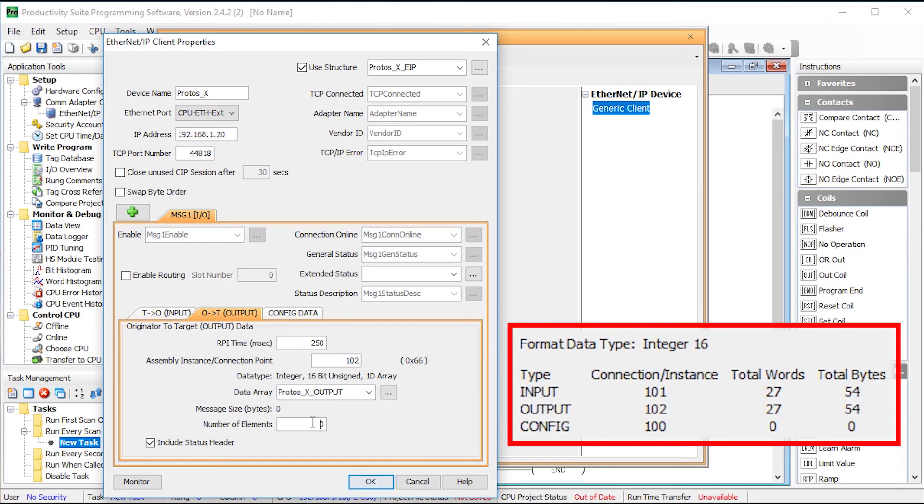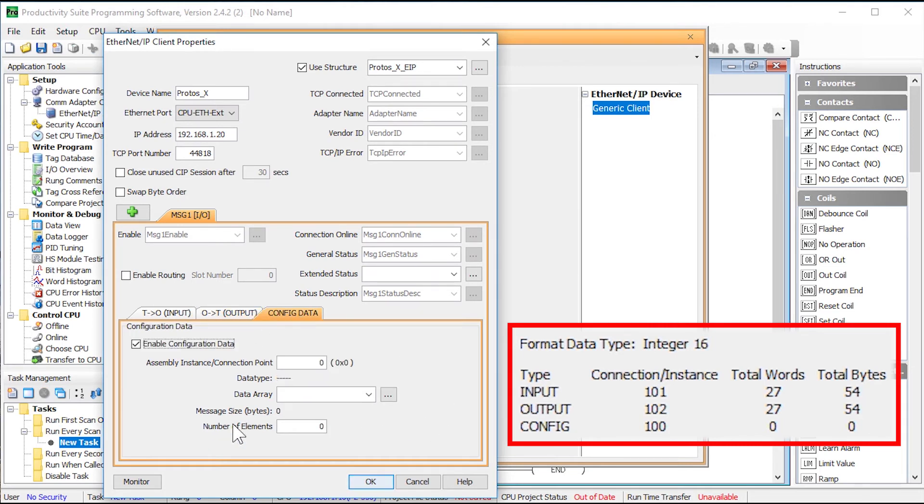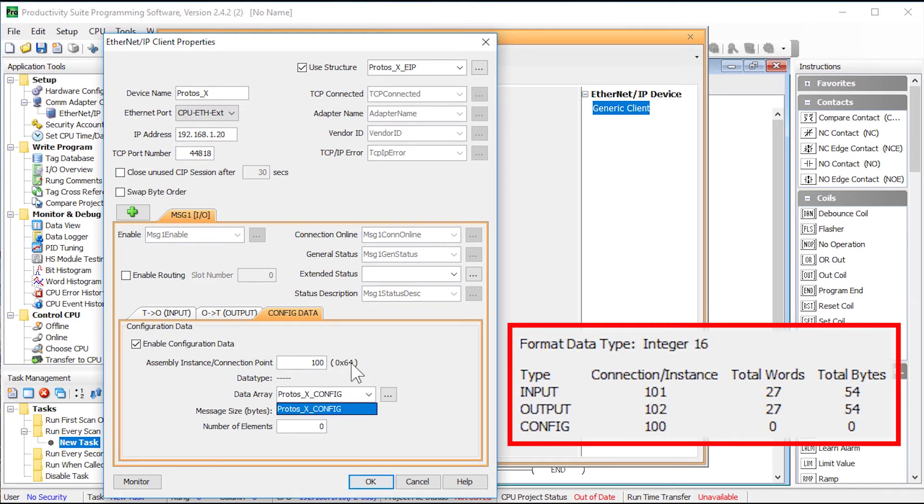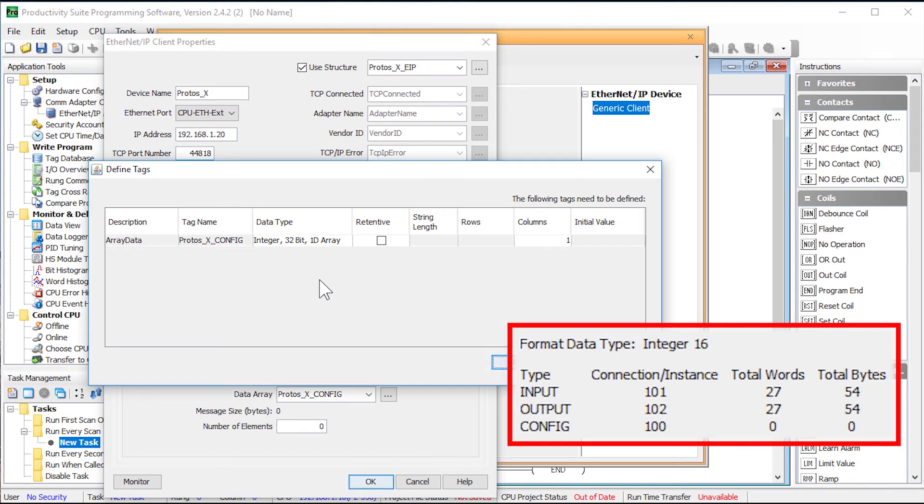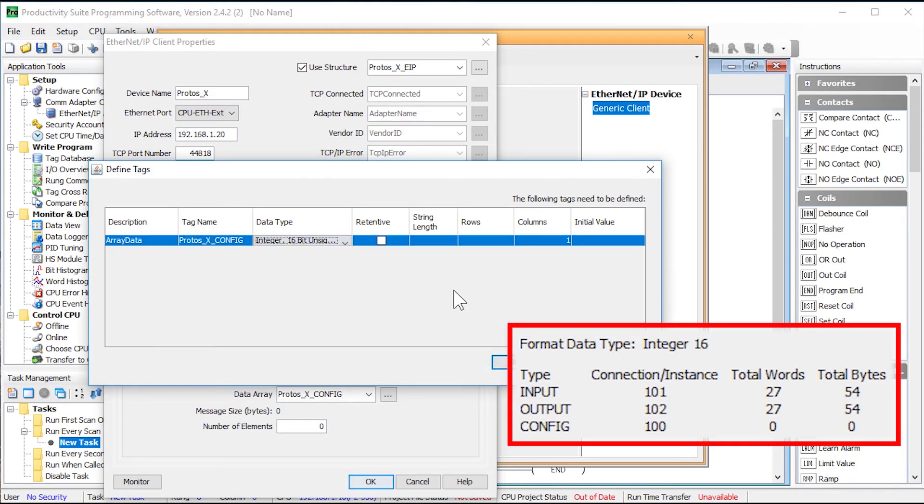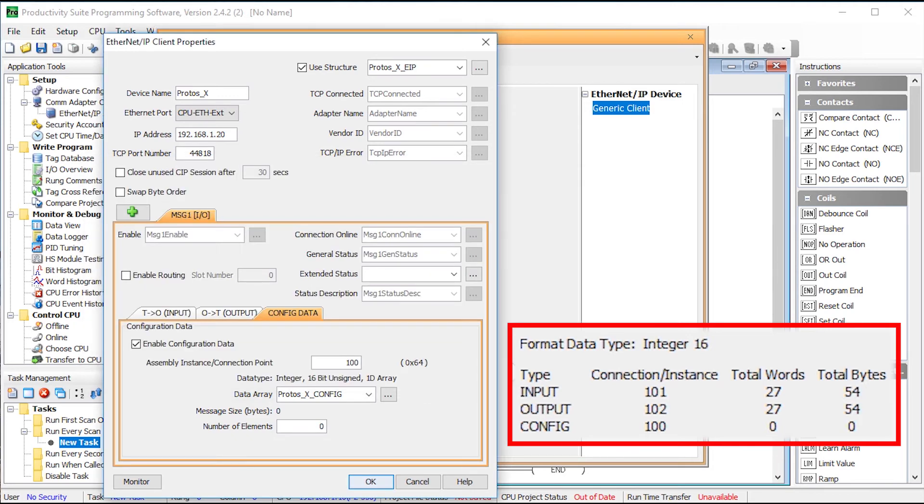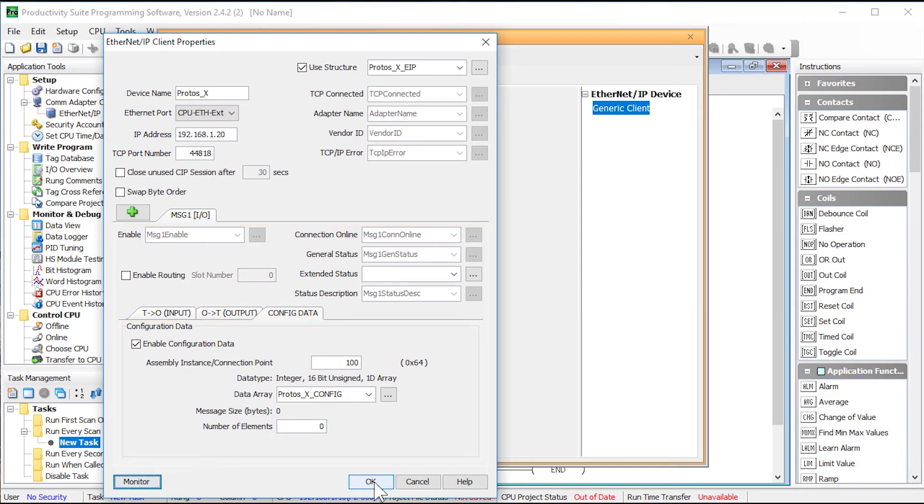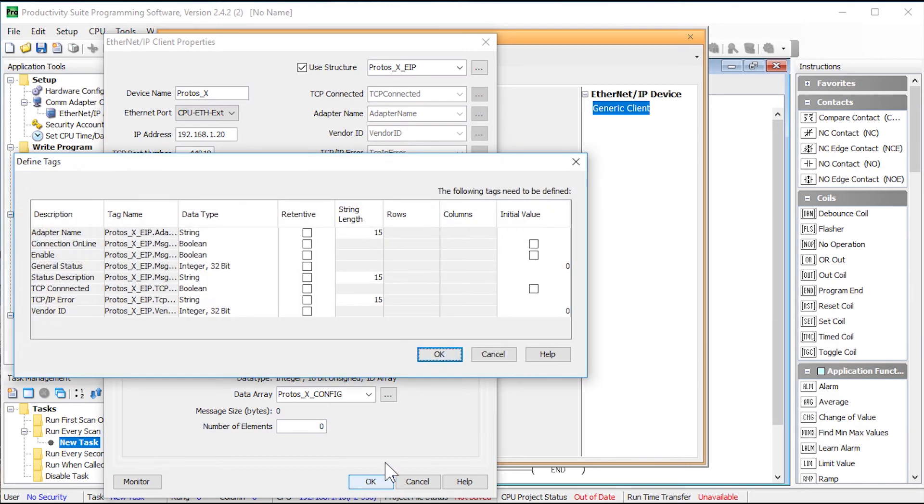Change the number of elements to be 27. Now to set up the configuration word. Enter the assembly instance of 100. I am going to enter in the following data array and when I click on the number of elements this dialog will show up. Change the data type to 16 bit unsigned and the columns can remain as 1. Select OK and then the number of elements can remain as 0. When we select OK here we will be completing the structure for this device.